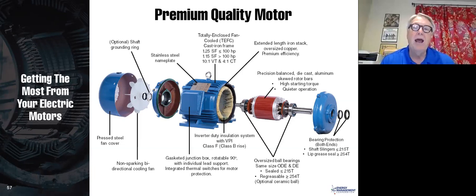Everyone does that, but how many times at your company would somebody say, hey, I lost a motor, and you go to purchasing and you say, I need a 10 horsepower, 1800 RPM motor in this frame size. And what does purchasing do? They go out and they say to 3 distributors, give me your price on a 10 horsepower, 1800 RPM motor. And what are they saying to the distributors of those motors? They're saying, please sell me the biggest piece of crap that you can possibly find in the world, because I have no concern about quality. All I care about is a price on a 10 horsepower, 1800 RPM motor. Well, guess what? All motors are not built the same. So let's talk very quickly about what differentiates a quality motor from a motor that is not so good a quality.